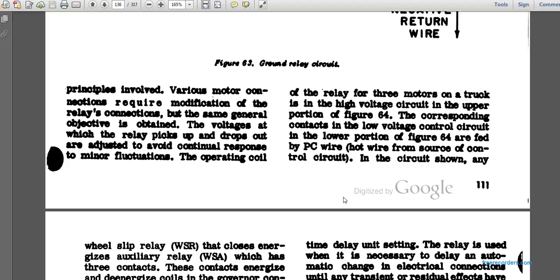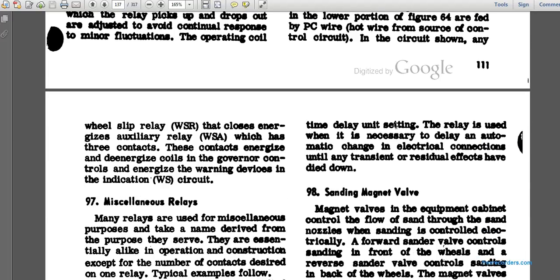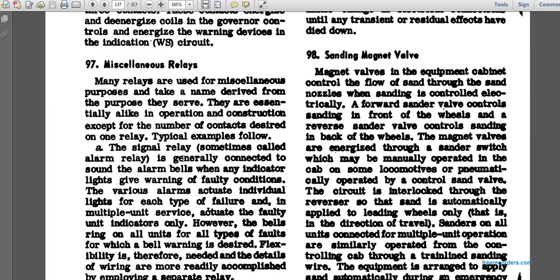The voltage at which the relay picks up or drops out is adjusted to avoid continual response to minor fluctuations. With three motors per truck, the high voltage circuit shown in the upper portion of figure 64 corresponds to the low voltage control circuit in the lower portion of figure 64, fed by the PC wire. In the circuit shown, any real wheel slippage causes the relay to close and energize an auxiliary relay, WSA, which has three contacts. These contacts energize the governor controls, the warning device, and the WS circuit indication.